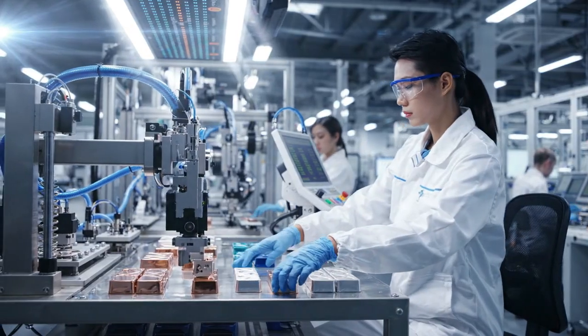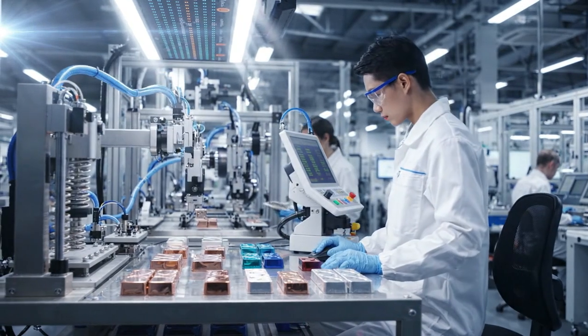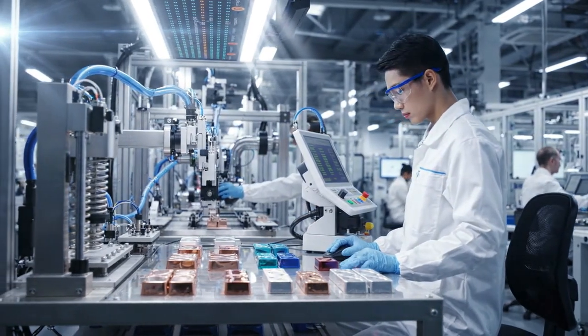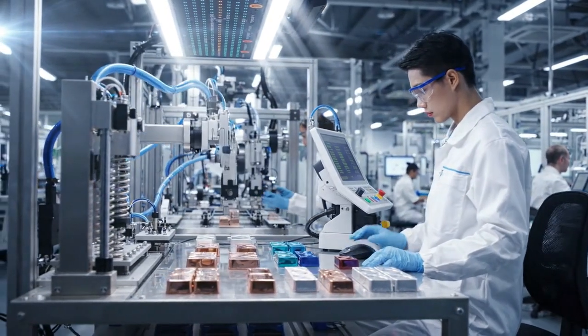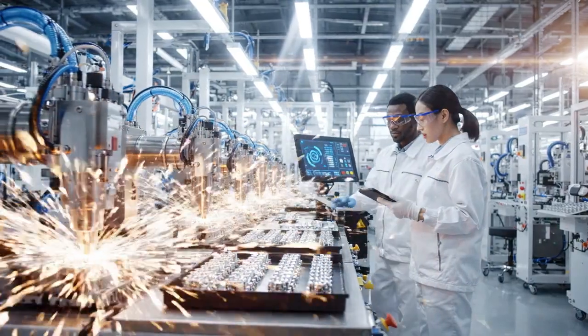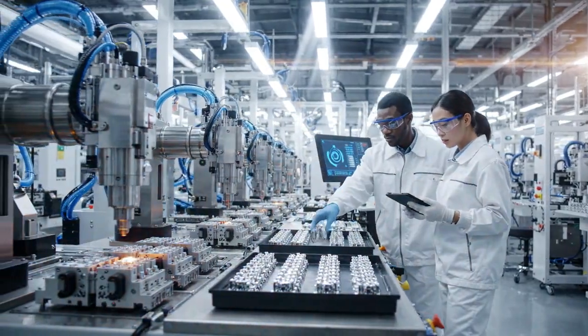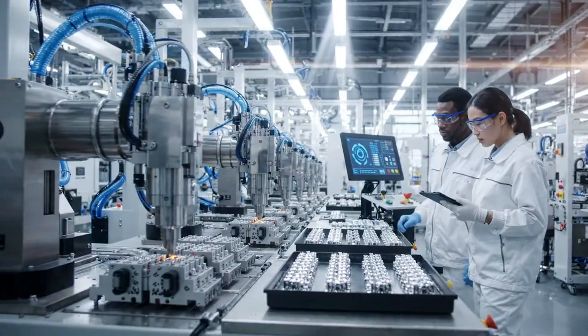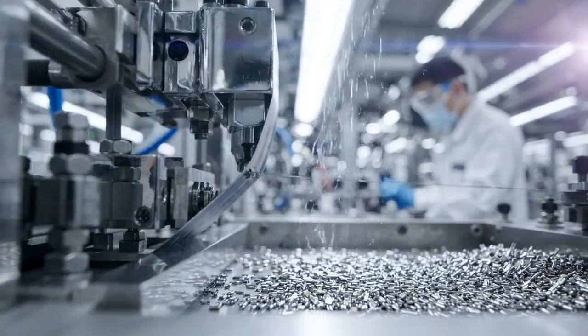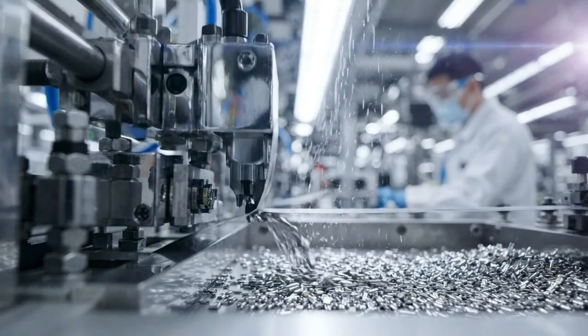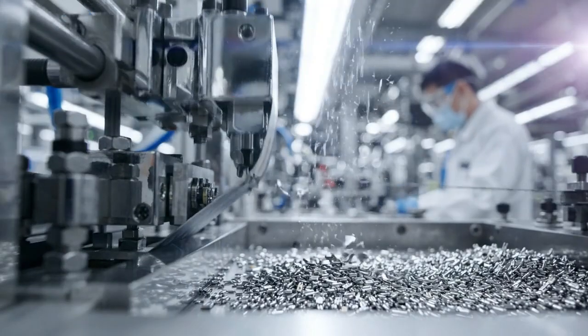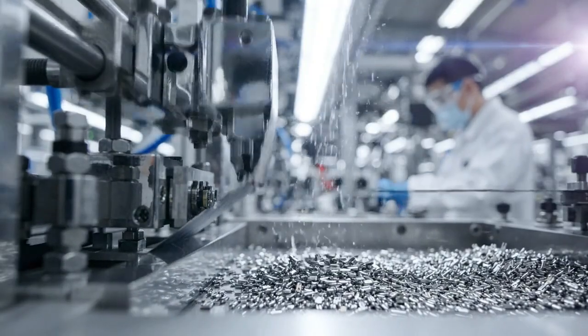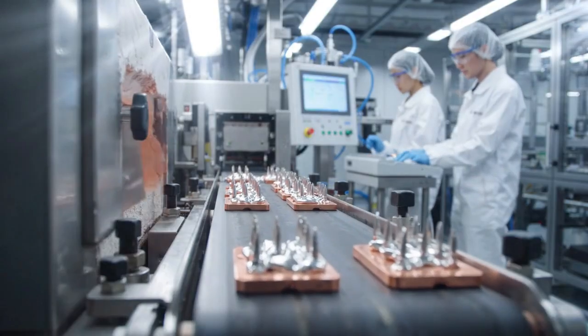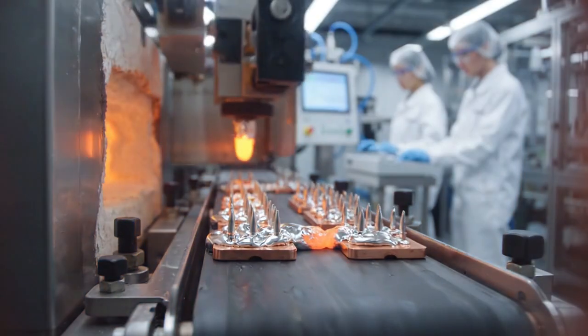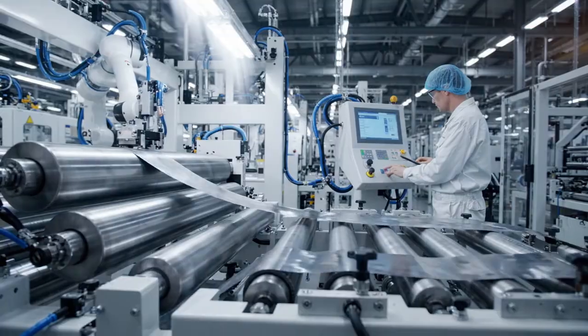Material quality directly determines breaker performance. Out-of-specification contact material could weld during fault interruption, leaving the circuit unprotected. Contact manufacturing produces millions of precisely formed silver alloy tips that must survive thousands of switching operations and dozens of fault interruptions. Brazing creates a metallurgical bond between the silver contact and its copper carrier that will never separate, even under the extreme forces of repeated fault interruption.